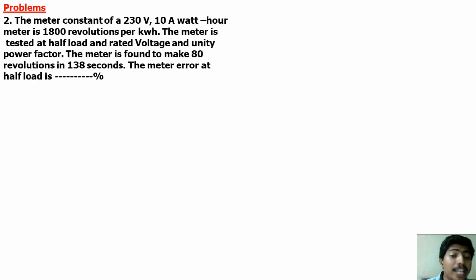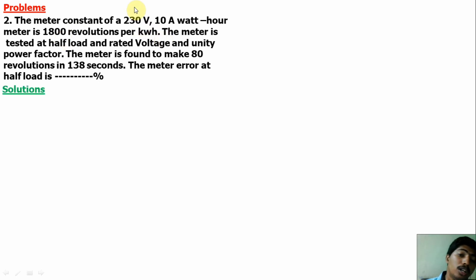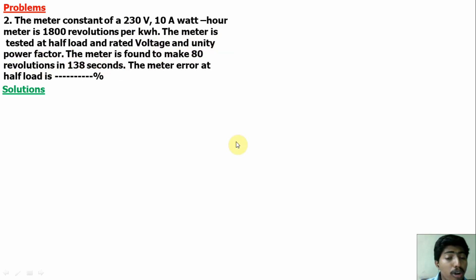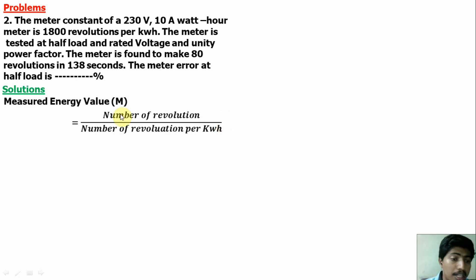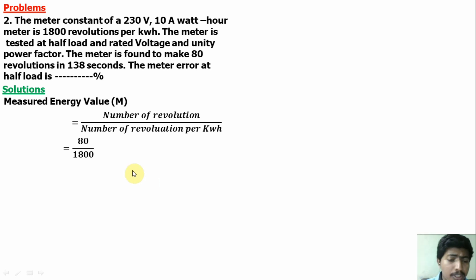Second question — here we have to find the error value. Meter constant is given as 1800 revolutions per kilowatt hour. Input voltage is 230 volts, rated current is 10 amps, power factor is unity. The meter is tested at half load and rated voltage — half load means current is half. Number of revolutions is 80 and time is 138 seconds. First, measured value equals 80 divided by 1800, giving 0.0444 kilowatt hour, that is 44.44 watt hour.